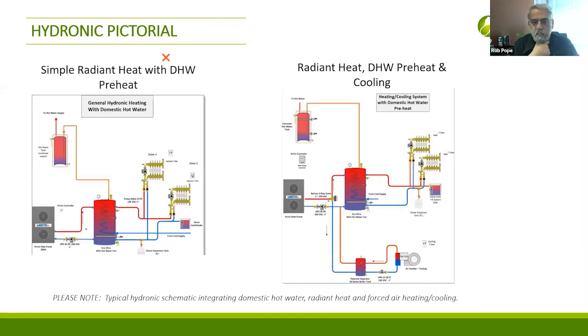So here's a pictorial of what is going on with the air to water system. You can see here on the left, it's just doing your radiant and your domestic. You've got your outdoor unit connected to your buffer tank. That buffer tank will have a preheat coil in it. So in other words, your street water comes in, and it doesn't go straight to your hot water tank. On its way, it goes through your buffer tank, which is a tank full of warm water. So it preheats that city water before it goes to your domestic tank, and your domestic tank has less work to do to get it to temperature.